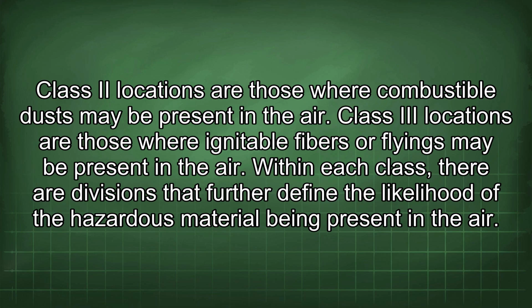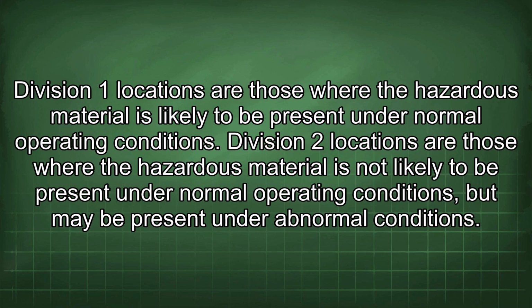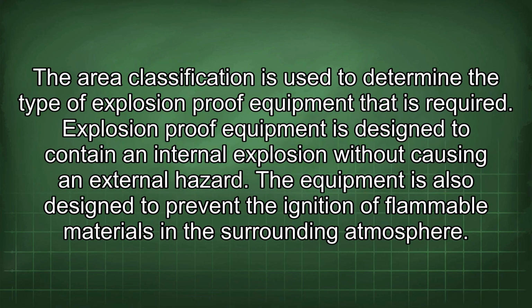Within each class, there are divisions that further define the likelihood of the hazardous material being present in the air. Division 1 locations are those where the hazardous material is likely to be present under normal operating conditions. Division 2 locations are those where the hazardous material is not likely to be present under normal operating conditions, but may be present under abnormal conditions. The area classification is used to determine the type of explosion-proof equipment that is required. Explosion-proof equipment is designed to contain an internal explosion without causing an external hazard. The equipment is also designed to prevent the ignition of flammable materials in the surrounding atmosphere.